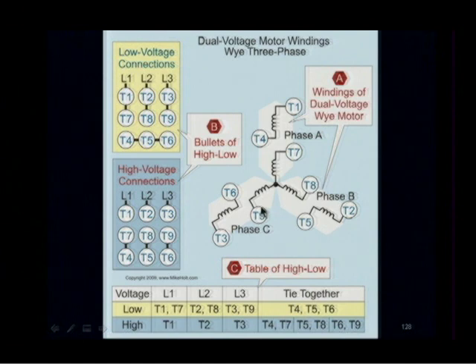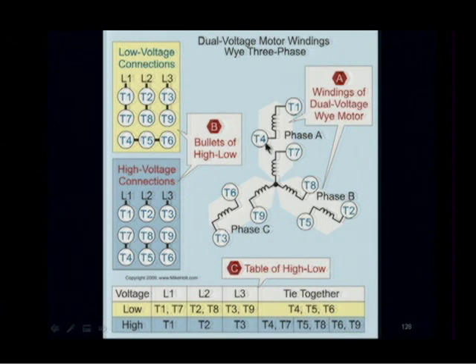And there is a method that you can use, and I don't recall the whole method, but again, you can go on the internet and find it probably, where you can tie them together. It's something like you tie 2 of the 3, like 7 and 8 together to one line, and then you just bump the lead 9, and then you put an ammeter on each of the other, like the 1 and 4, to find their polarities.